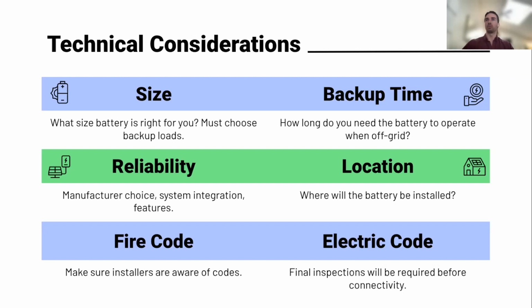Backup time is briefly touched on here, but it's very difficult to say how long a battery will last for folks without including a lot of assumptions into that model. We could assume, if there's no sun available and there's only 20 kilowatt hours of battery storage based on the amount of loads wired to that battery, we could give you a general understanding of how long that battery will last.